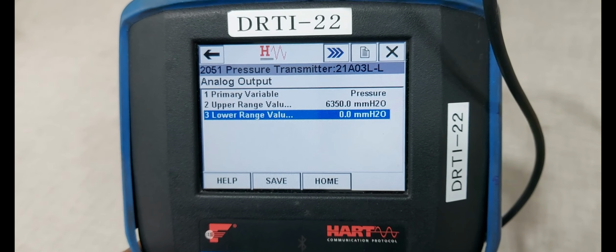Go into the home menu. Next we are performing the pressure calibration. Select the service tools and the maintenance and the pressure calibration menu. First we are doing the lower sensor trim. If you are doing the lower sensor trim, high side and low side equal pressure is minimum required. We are connecting the tube from the high side and the low side.